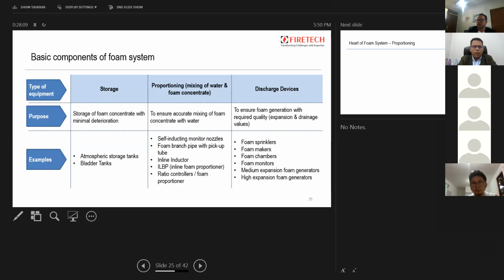Yeah, so what are the basic components of a foam system? Any foam system consists of basically three main components. One is how the foam is going to be stored, that is the storage. The second is how the foam concentrate is going to mix with the fire water, that is the proportioning. And the third ultimately is the discharge device, which actually converts the foam solution into foam. So let us look at each of the system components one by one. Storage. The purpose of the storage device is basically to store the foam concentrate with minimal deterioration. Examples of these are atmospheric foam storage tanks and bladder tanks.